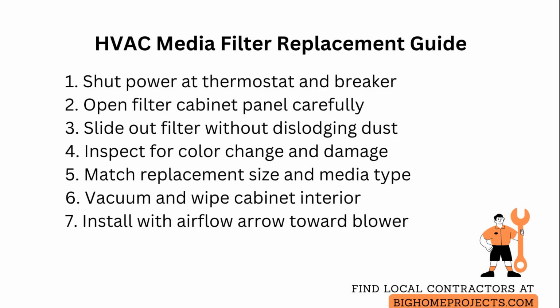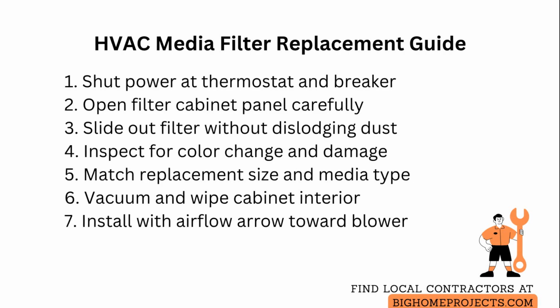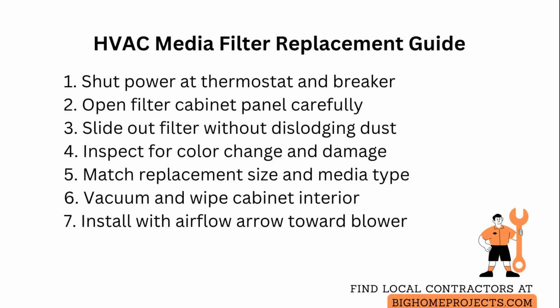bypass or improper fit. Measure the filter frame and media depth, and confirm the replacement matches the exact size and media type to preserve the design pressure drop and particle capture rate.